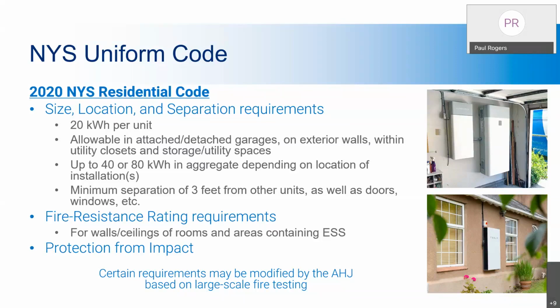For instance, the separation distance from each unit has to be at least 3 foot, and it also needs to be 3 foot from windows and doors or any type of egress. Fire-resistance ratings also need to be on the roof, so you can't have any roof that is open to the air where you have no sheetrock or any type of gypsum board above it. So fire rating is going to have to be on the walls and ceilings of the room and the areas containing that ESS. If you have these in your garage and the ceiling does not have any gypsum board, that 5/8 inch gypsum board, you're going to have to put it up there in order to comply with the code. And also the protection from impact.